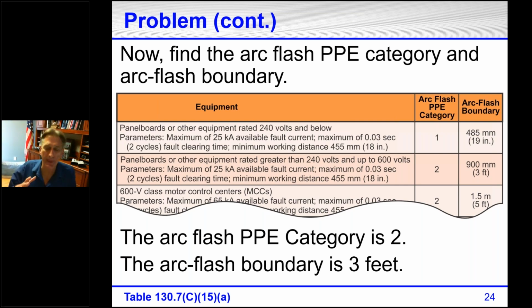All right, so I know plenty of contractors out there. I know there are plenty of companies that are trying to do the right thing. Maybe they're hired to do some voltage testing or look for problems in a panel board in an office building. And so they've got to open the panel board, take the cover off while everything is energized, if they're looking for and even testing voltage and amperage. They go into this office building, they find this panel board or multiple panel boards, and before taking the cover off, they know that they're going to do voltage testing, so they know they have to wear PPE. They look on the panel board, there is no label. The owners of the building have not had the panel boards labeled.